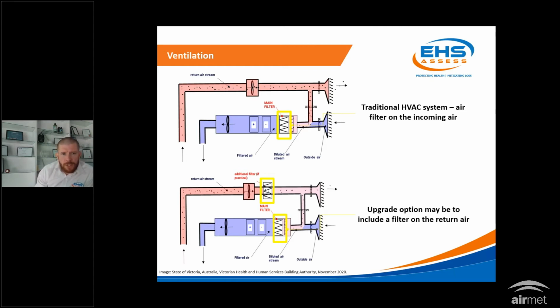The pink diagram shows the return air. These systems work on the principle of supplying air to an area and returning that air. The reality is these systems don't dump all the return air back out onto the street - they actually have a fairly large recirculated air component. So if you've got one of these systems supplying multiple areas, it's possible it could actually be contributing to an issue rather than solving one. So it's really important to understand what system you have, how it's working, and how you can make it work for your needs.